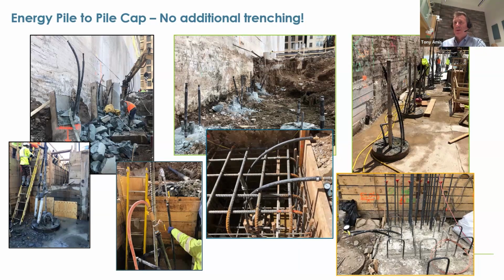What you see here is the piles being trimmed down, top left. The geo loops were pretty bomb-proof from the abuse they were given. This surplus loop was cut down eventually, and on the bottom left you see those white sleeves removed, then we were able to cut the loops down, do a flush test, pressure test, and give the green light for the foundation contractor to fill and concrete the pile cap.